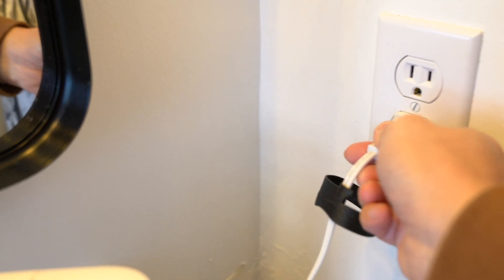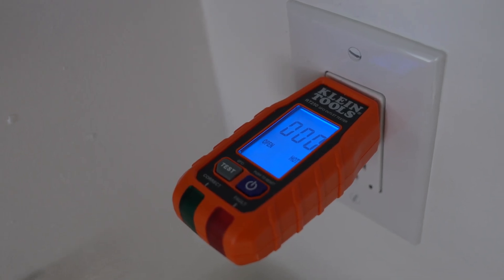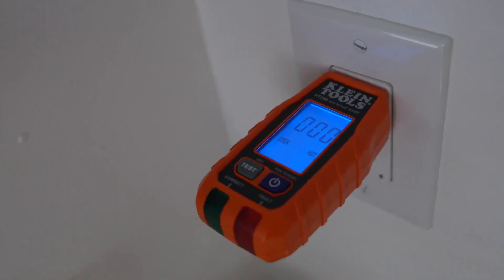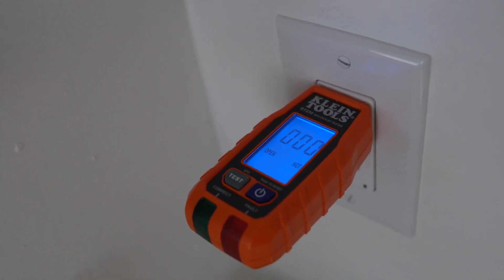To address the issue, try plugging a small appliance, lamp, or device into the outlet or any other outlet downstream. This would help dissipate phantom voltage by providing a path to ground. If the issue is truly phantom voltage, the reading should disappear.